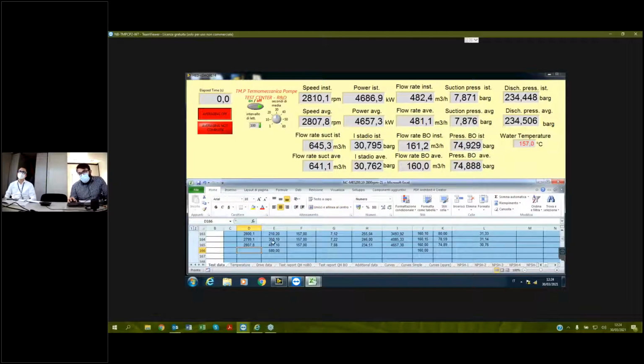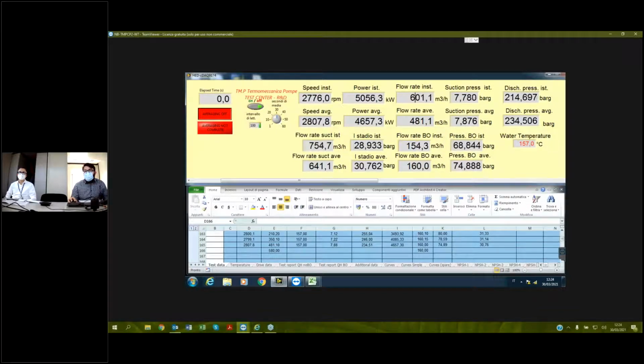Now my colleague operating the discharge valve literally changes the flow. For this test, we go to 480 of capacity, about. Okay, you can see that the flow is increased.